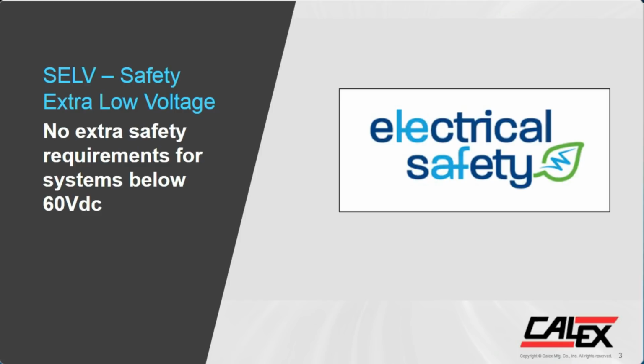So what that means basically for DC to DC converters is typically, unless your voltage is above 60 volts for a DC to DC, it's not applicable, because typically, if you're using a DC to DC where there's AC power, or what's referred to as an AC main, there'll be an AC to DC power supply involved, which has an isolation transformer. So in standard industrial applications where you're coming off an AC main, as long as you stay below the 60 volts, you don't have to design for these requirements.